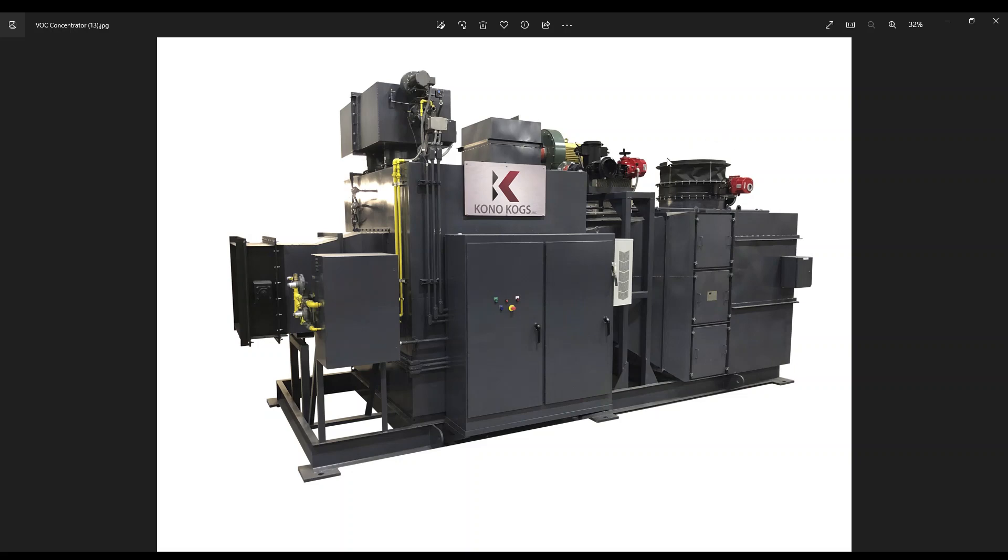And then that air then passes through out of the wheel housing into this desorption blower. And this is a little T-damper. You can see how small that is compared to the inlet. You can see that's such a significant savings in airflow that all those VOCs, 98% of those VOCs that came in here, are all captured in this smaller slipstream of 5,000 SCFM that goes out this damper. And this would go to atmosphere if we were bypassing, which typically you don't do, but it does have that capability for heating the unit and all the safeties that are required. Typically, it's running right to the RTO here and out to the inlet of the RTO for treatment. So physically, that's what a VOC concentrator looks like. This is the burner segment. There's a duct that comes up into here and then comes back down into here.